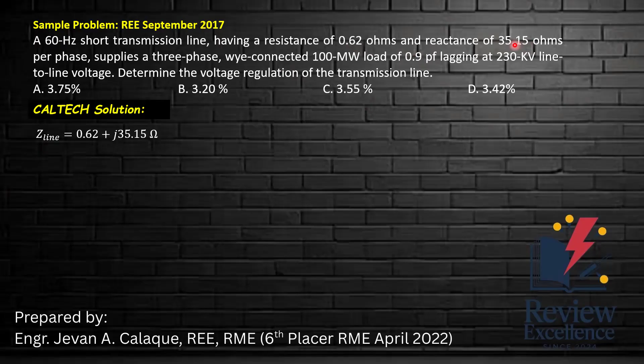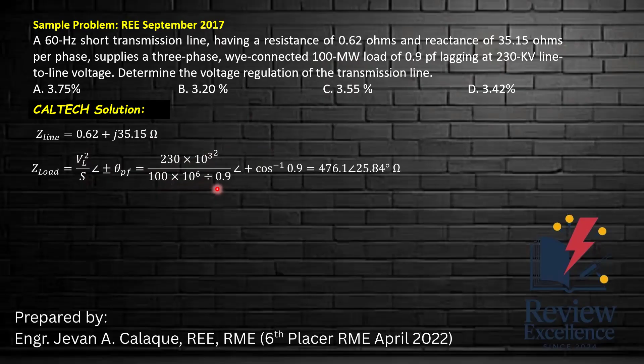How do we solve the load impedance? It is the receiving load voltage squared divided by the apparent power, at an angle of positive or negative power factor angle. The receiving voltage is 230 kV, or 230 times 10 to the power of 3. We square this and divide by the apparent power. Since the given power here is real power, which is 100 megawatts, we have 100 times 10 to the power of 6, and to get the apparent power we divide by the power factor of 0.9.